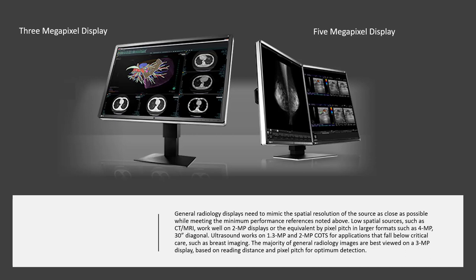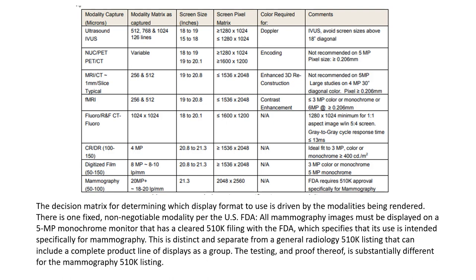The resolution of the display monitor can vary greatly. Usually we use between a 3 megapixel display and a 5 megapixel display for medical imaging, but we can use monitors with less resolution and more resolution as well. The decision for matrix resolution for determining which display format to use is driven by the modalities being rendered. There is only one fixed non-negotiable modality per the US FDA standard and that is for mammography.